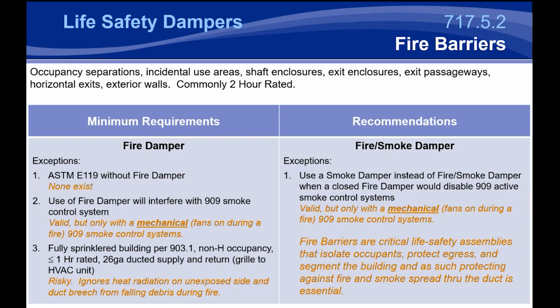Certainly the rated barrier may degrade if it's using gypsum as its main protection, which is very common for 1 and 2 hour rated walls. And there is the potential for a duct breach. So if you've got multiple stories and there's a fire on a story above, that duct could potentially get dislodged by something falling during the fire, and there will be an open penetration at that point.